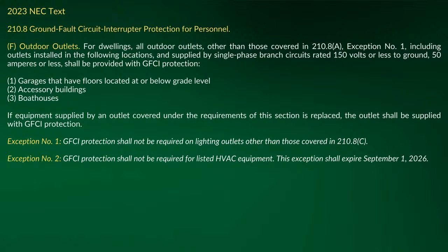If you look at the 2023 NEC and the substantiations from the code-making panel, it's interesting. In 210.8D the panel was very specific that it applied to both cord-and-plug connected and hardwired equipment, with substantiation. But when you got to 210.8F, they made no such mention. Remember, 210.8D2 says regardless of vintage, so they were specific there. But out here on outdoor outlets, they left it open on hardwired versus cord-and-plug, and some people claimed it applies to everything outside. I don't agree with that.